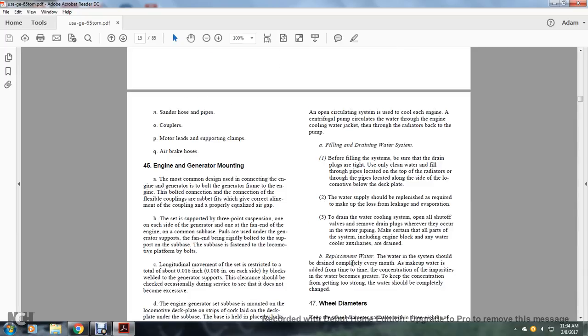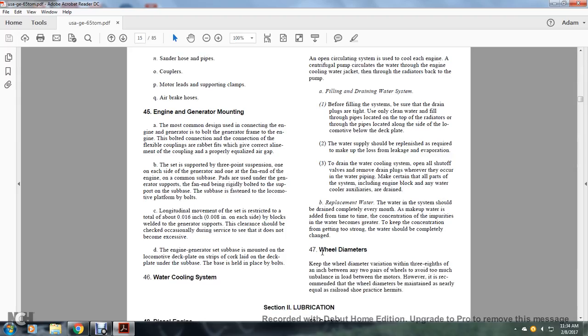Section 45, Engine-Generator Mounting. The most common design uses a flexible coupling with rabbet fits for the connection between engine and generator, ensuring correct alignment and properly equalized air gap. The set is supported at one point on each side of the generator and one point at the fan end, with the engine on a common sub-base. The sub-base is fastened to the locomotive platform by bolts. Longitudinal movement of the set is restricted to 16/1000 of an inch total, or 8/1000 of an inch on each side.